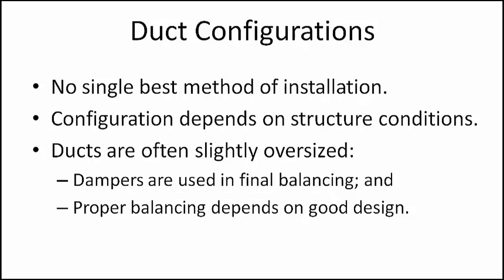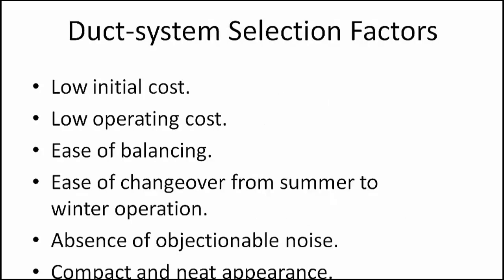Small residential installations usually are designed by the HVAC contractor. There are several requirements that should be met in order to provide both economy and good performance for the homeowners. These requirements include: low initial costs, which depends primarily on simplicity of design and minimum oversizing of the ducts; low operating costs, which depends on whether the system is designed for the minimum practical pressure loss; ease of balancing; ease of changeover from summer to winter operation; absence of objectionable noise; and compact and neat appearance.